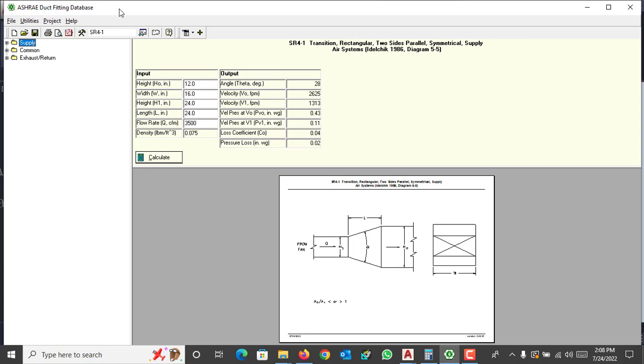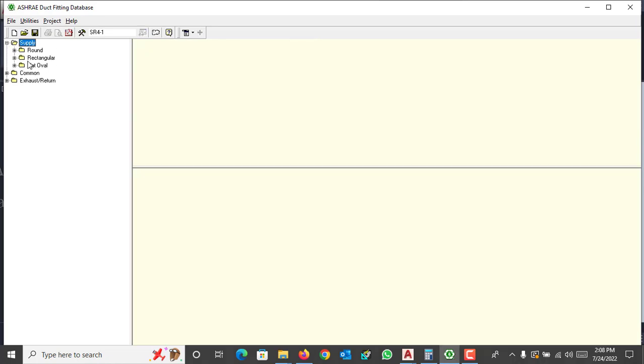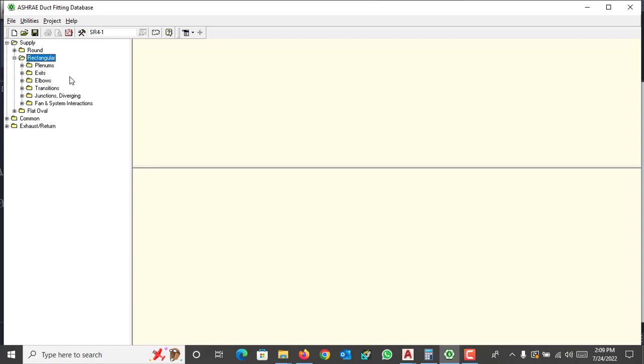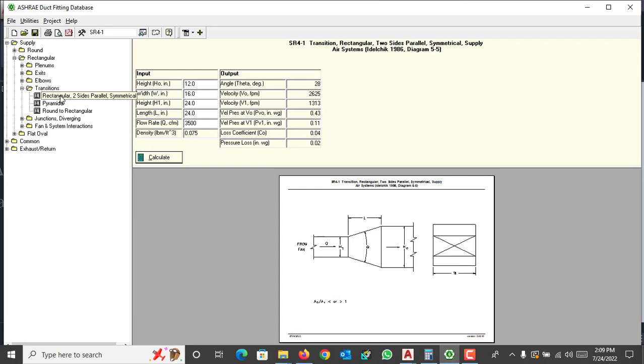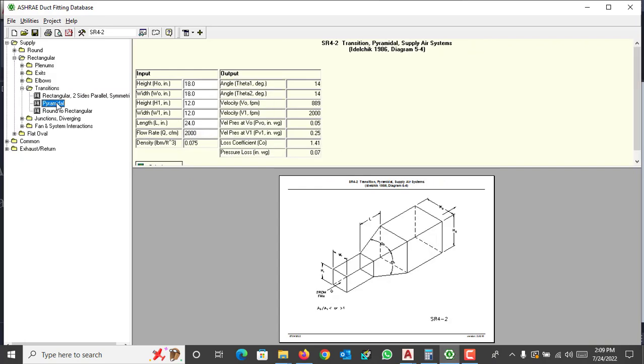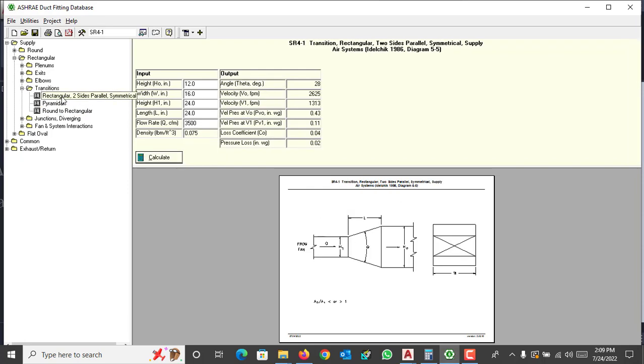Now we will start with this supply duct. In the ASHRAE Duct Fitting Database — I will provide a link in the description so you can download and use this software — select 'Supply' and then 'Rectangular.' Here you can see the fittings available for ESP calculation. I will select 'Rectangular Two-Side Parallel Transition,' specifically the 'Rectangular Two-Side Parallel Symmetrical Supply Air System' fitting.